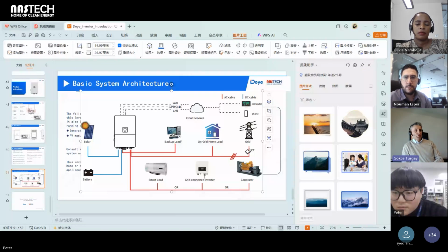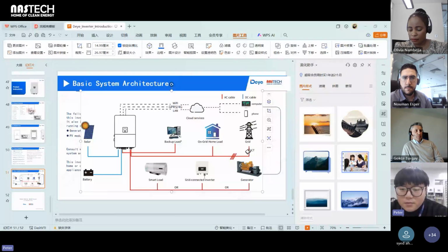Peter, if we set voltage to 250 volt instead of 850 volt, charging current will remain 80 plus 80, or will it increase? I'm not sure I understand this question. I think he means that if the battery voltage is 250 volt instead of 850 volts, can we increase more than 80 amp current? The answer is no. The 80 amp is the maximum limitation. So no matter how high your battery voltage is, the 80 amp is decided. So if you want to reach higher battery power, up to the 80 kilowatt maximum, you should increase your battery voltage.